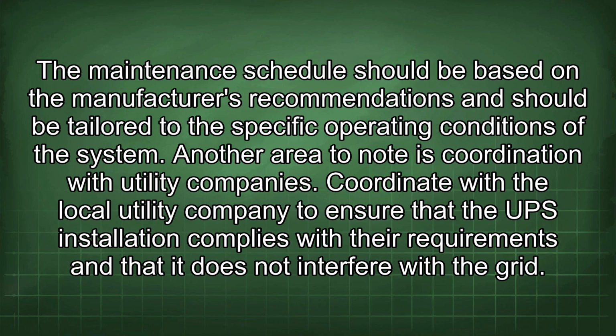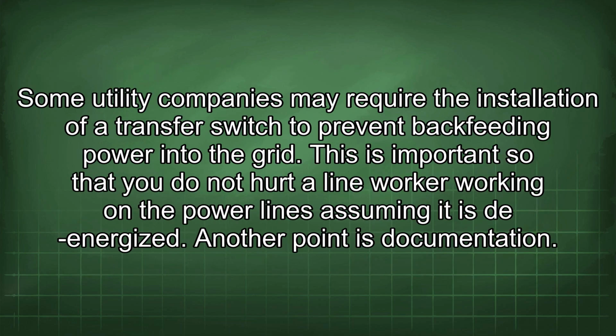Coordinate with the local utility company to ensure that the UPS installation complies with their requirements and that it does not interfere with the grid. Some utility companies may require the installation of a transfer switch to prevent backfeeding power into the grid. This is important so that you do not hurt a line worker working on the power lines assuming it is de-energized. Another point is documentation.